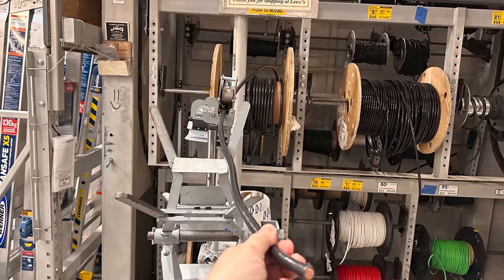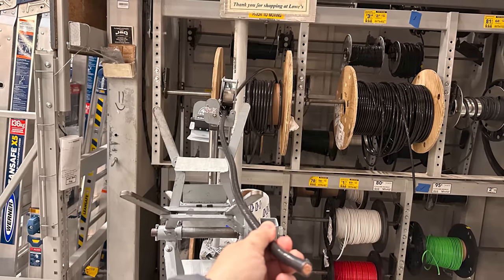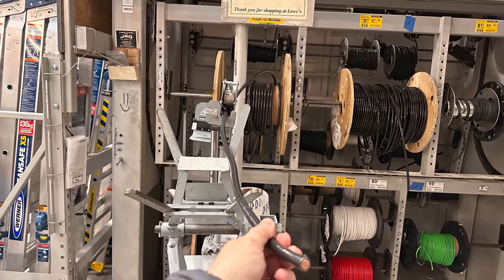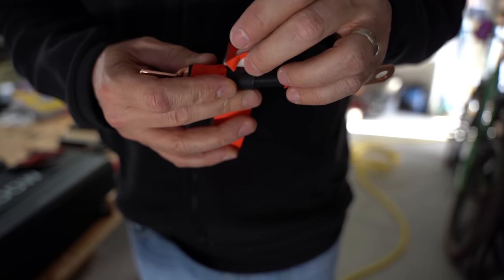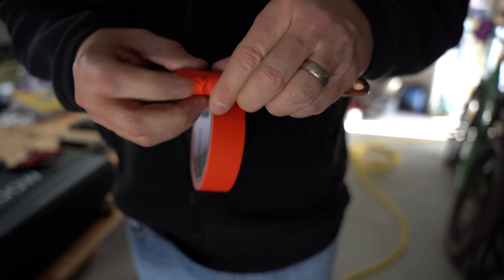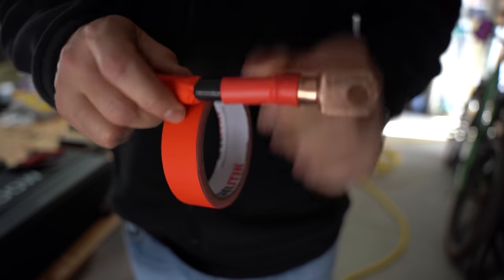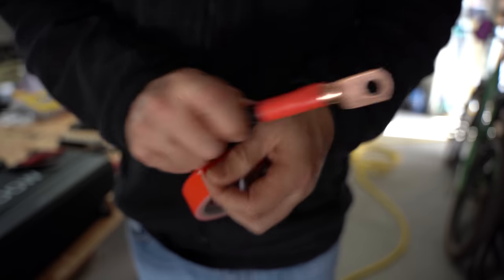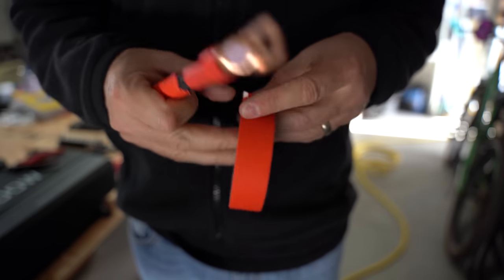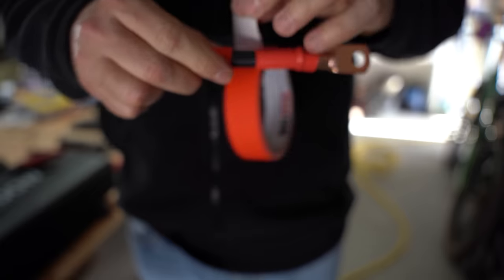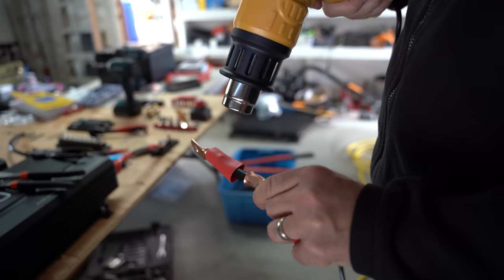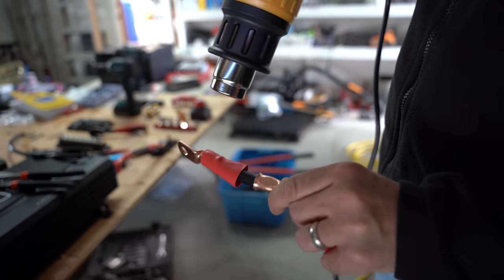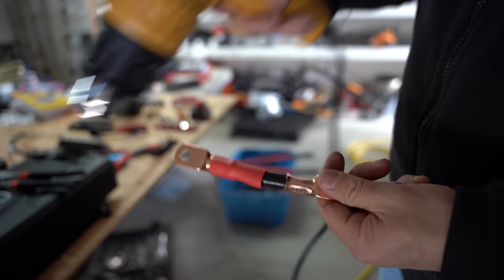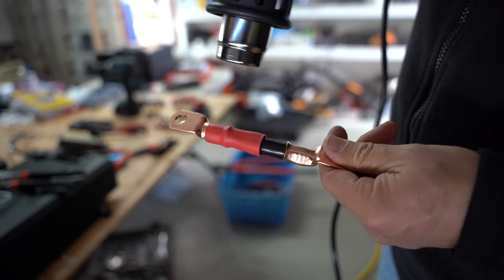One other pro tip. When I purchased the 2-aught gauge wiring at Home Depot, they had only black cable. For this part of the video, we're connecting the positive terminal of the inverter to the positive terminal of the battery. So I went back and I wrapped the black cables with red tape. Ideally, you want to purchase red cables, but we improvised here. Additionally, when adding the shrink wrap to the cables, put red shrink wrap on the positive cables and black shrink wrap on the negative cables.